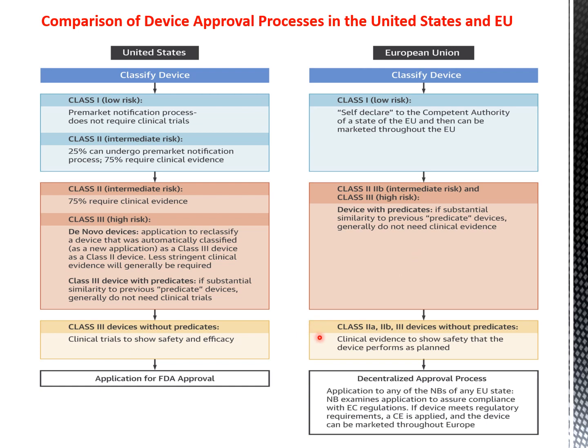And for Class 2A, 2B and 3 devices without predicates, clinical evidence is required to show safety and that the device performs as planned. And finally, a decentralized approval process is seen. The application goes to any of the NBs of any EU state, NB being notified body, which examines the application to assure compliance with the EC regulations, and if the device meets the regulatory requirements, a CE, conformité européenne, is applied and the device can be marketed throughout Europe.